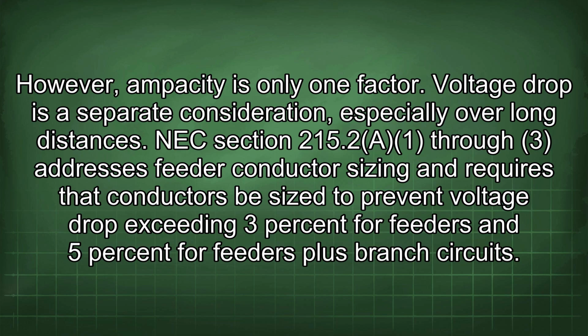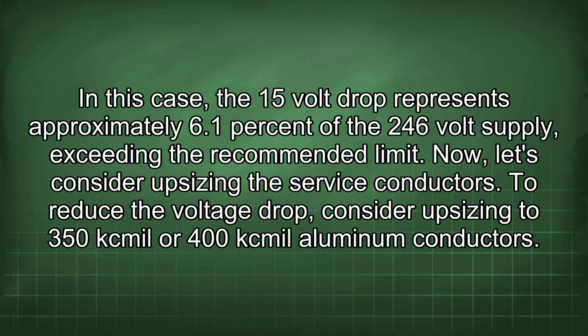NEC Section 215.2(A)(3) addresses feeder conductor sizing and recommends that conductors be sized to prevent voltage drop exceeding 3% for feeders and 5% for feeders plus branch circuits. In this case, the 15-volt drop represents approximately 6.1% of the 246-volt supply, exceeding the recommended limit. Now let's consider upsizing the service conductors.